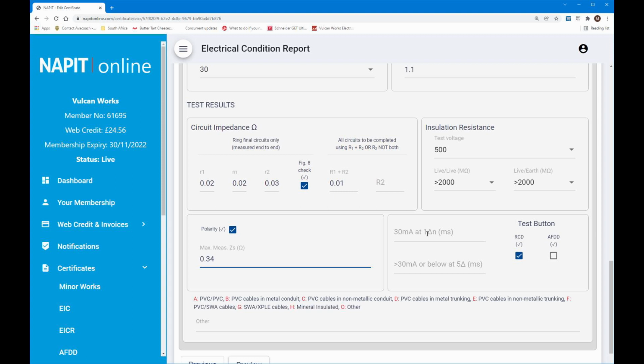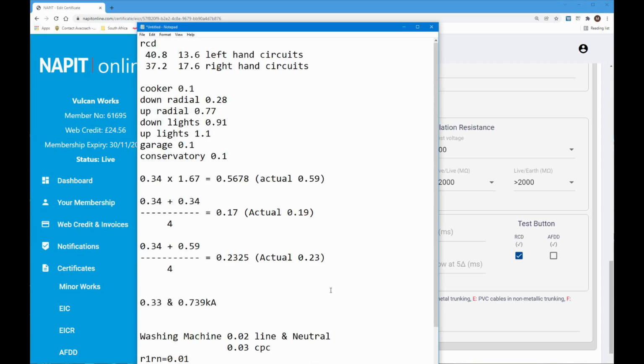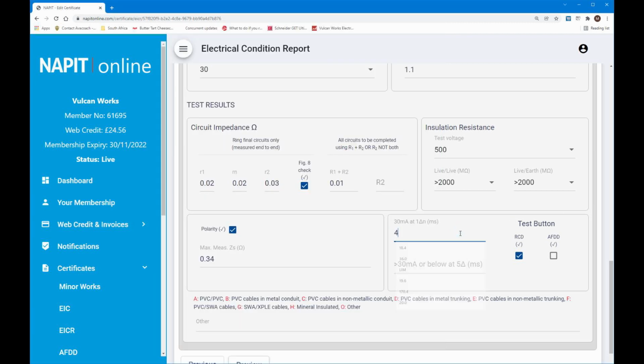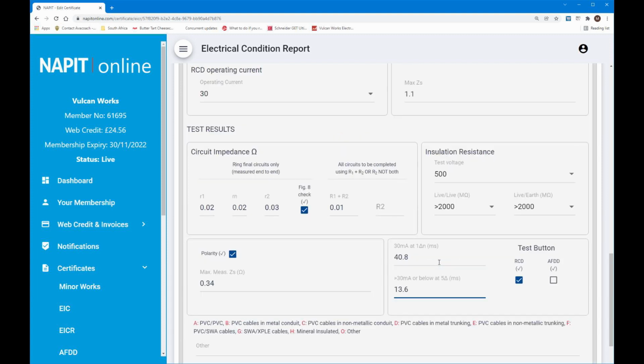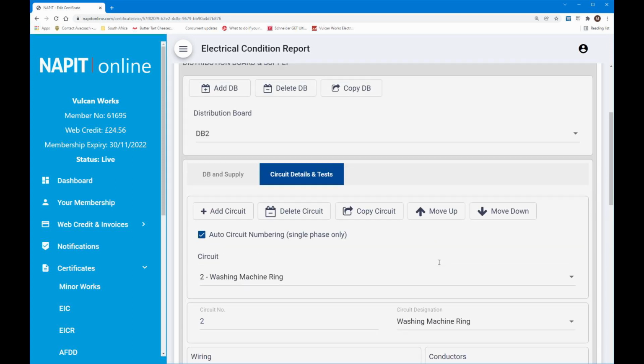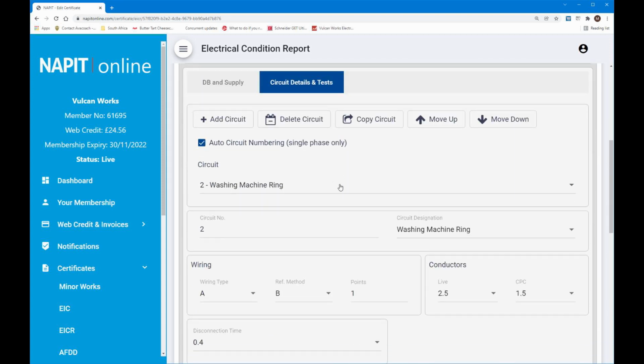0.34. Now the RCD for these two, the Conservatory is actually on the right hand side, so that's 37.2 and 17. Sorry, it's on the left hand side. So the Conservatory is on the left hand side, so it's 40.8 and 13.6. The RCDs on that one. So that's where we are with that particular ring, and we'll just do the other ring in the Conservatory, which was the Conservatory ring.